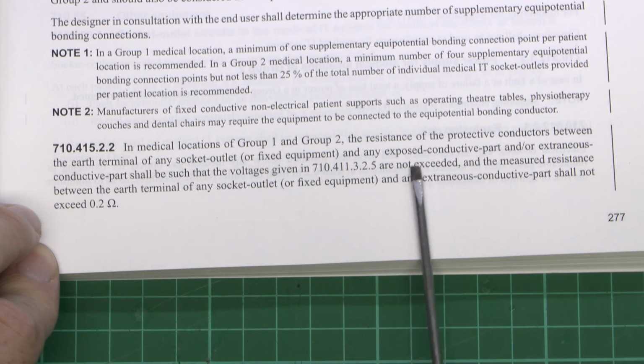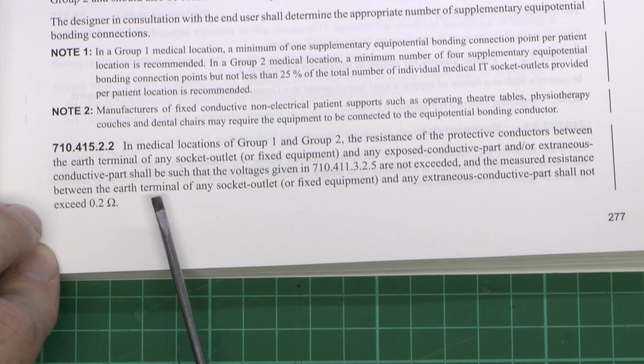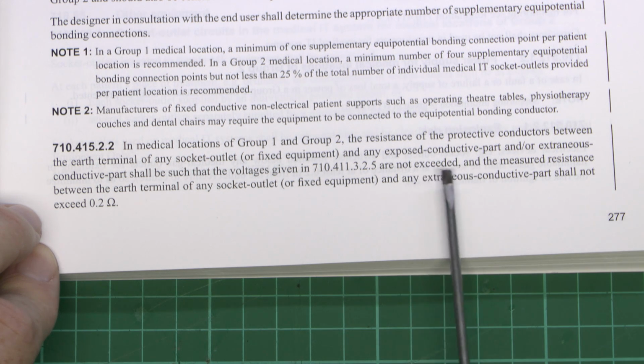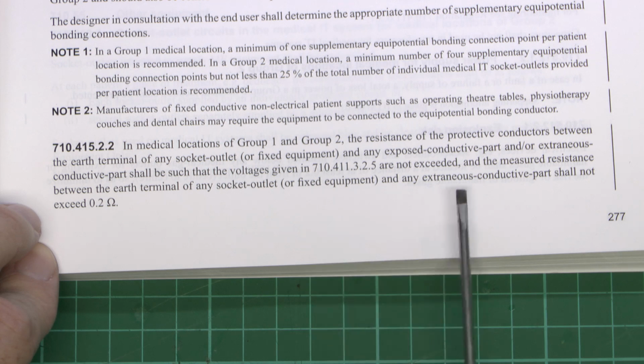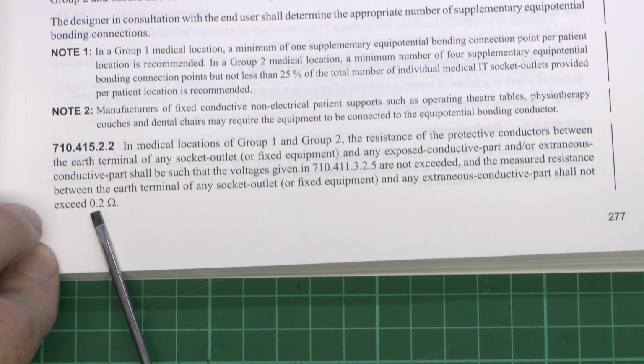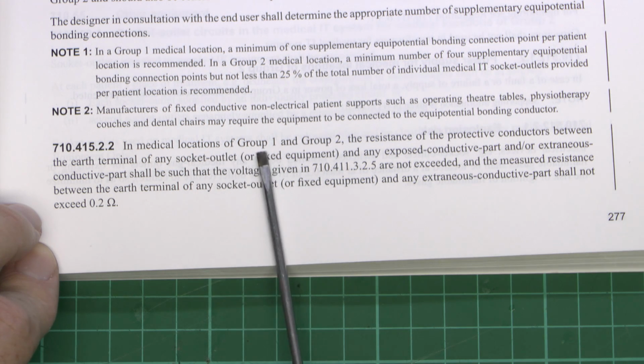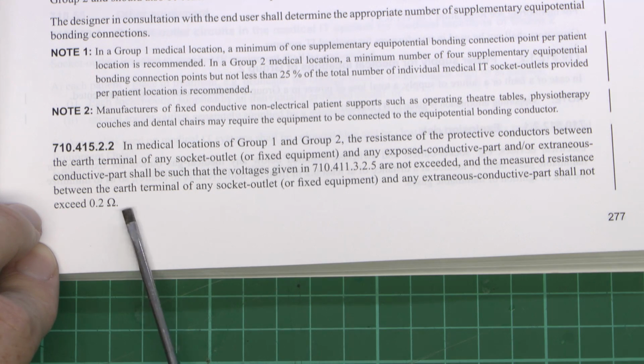710.415.22, this refers to the maximum resistance there, and the difference here now is that the measured resistance between the earth terminal of any socket outlet or fixed equipment and any extraneous conductive part shall not exceed 0.2 ohms, and this is for the locations Group 1 and Group 2. The previous one actually was 0.7 ohms for Group 1 and 0.2 for Group 2, so basically they're all now 0.2 ohms.